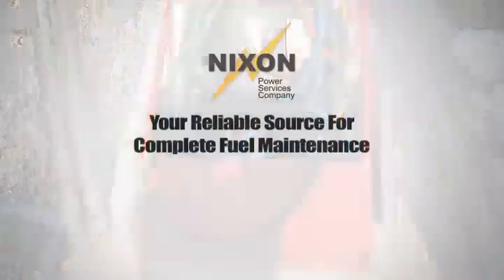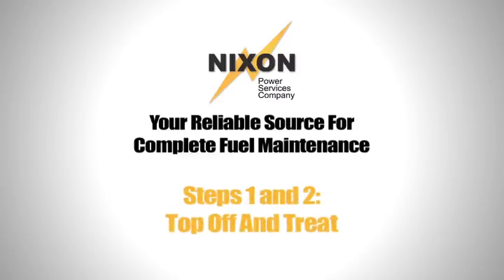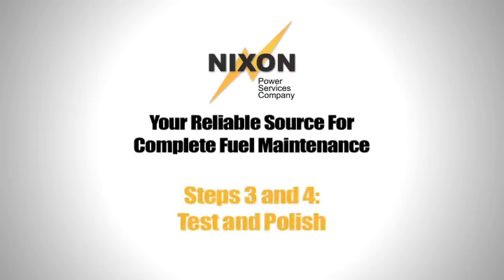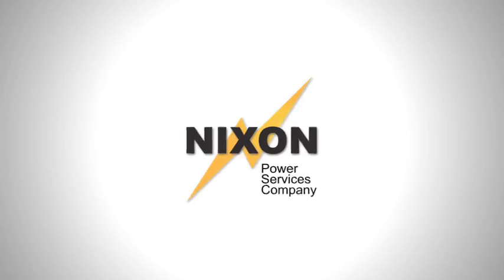So remember the Nixon Power Services Fuel Maintenance Program. A full tank is best. Use Steps 1 and 2, top-off and treatment, to prevent deterioration of your diesel and to maintain it in good condition. Use Steps 3 and 4 to check for fuel deterioration and correction should it be required. A standby power system cannot do its job without good fuel maintenance.